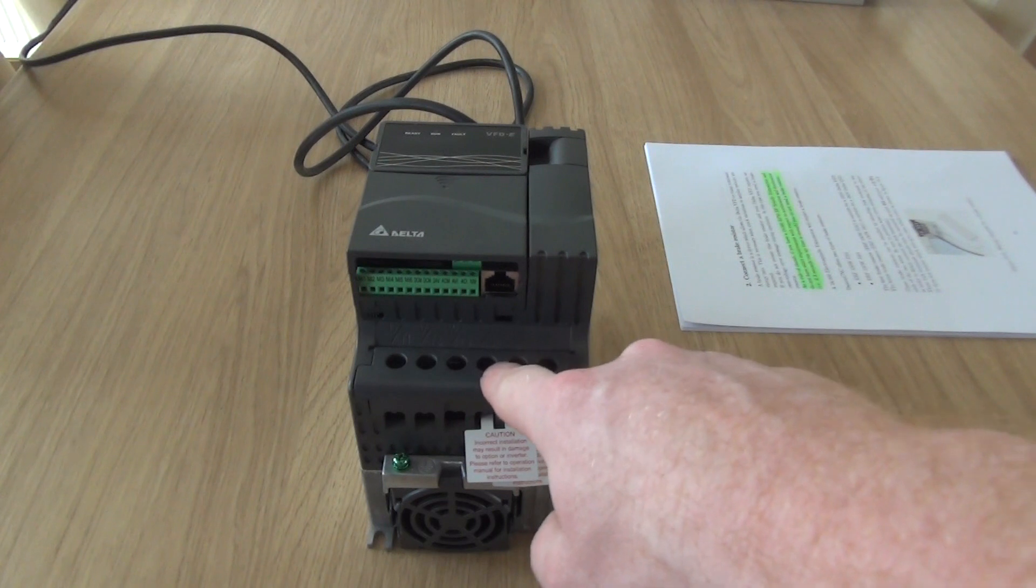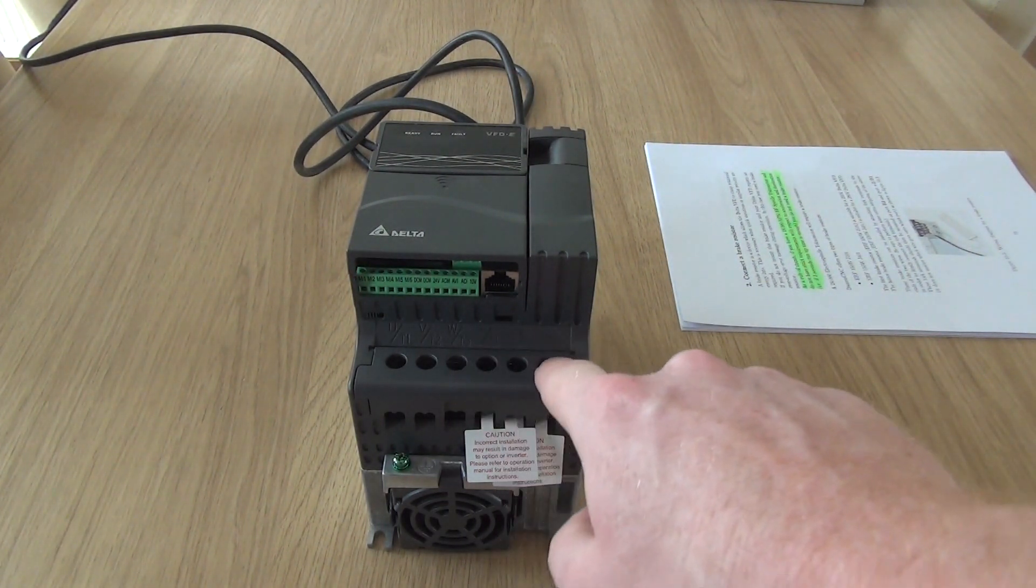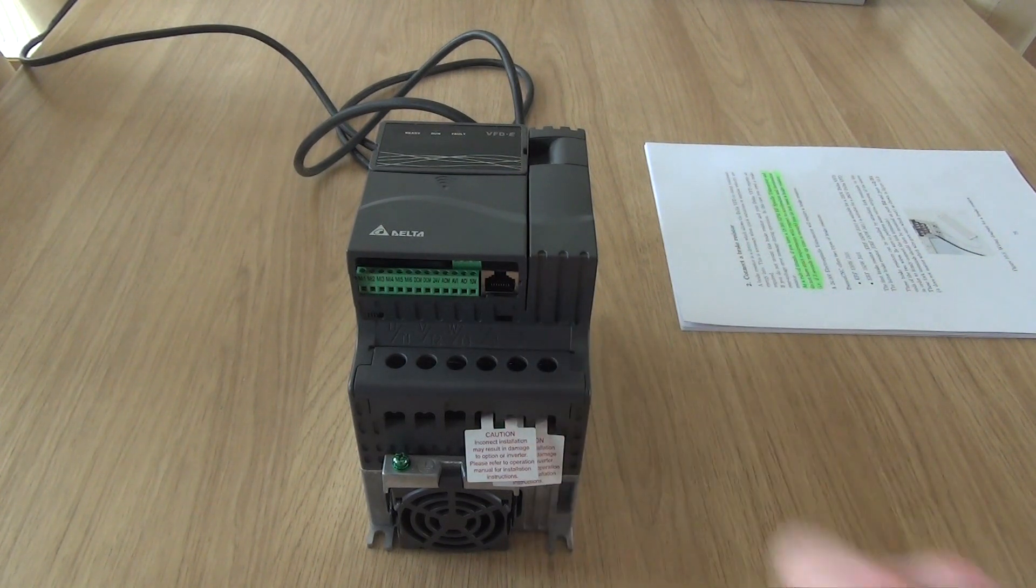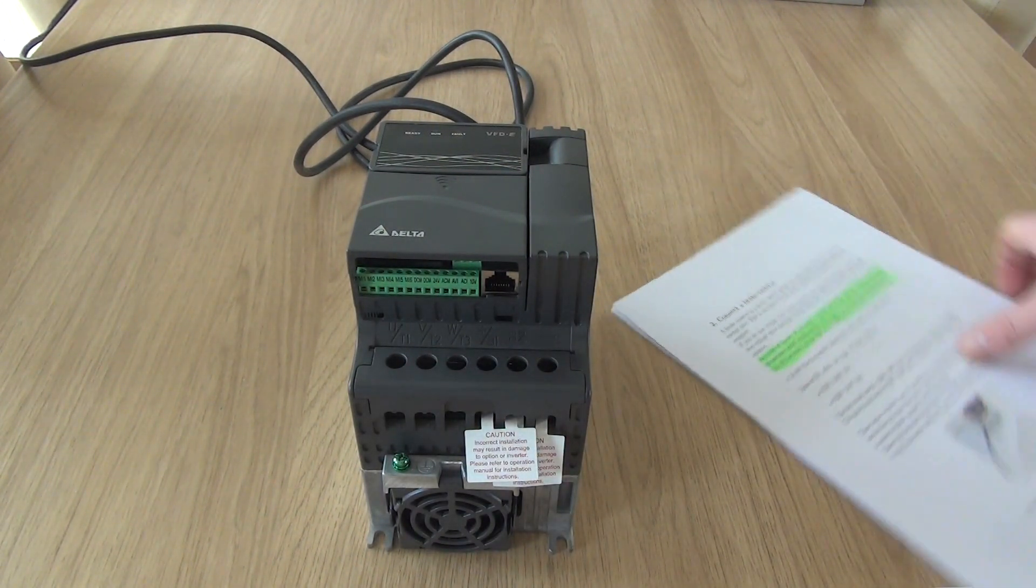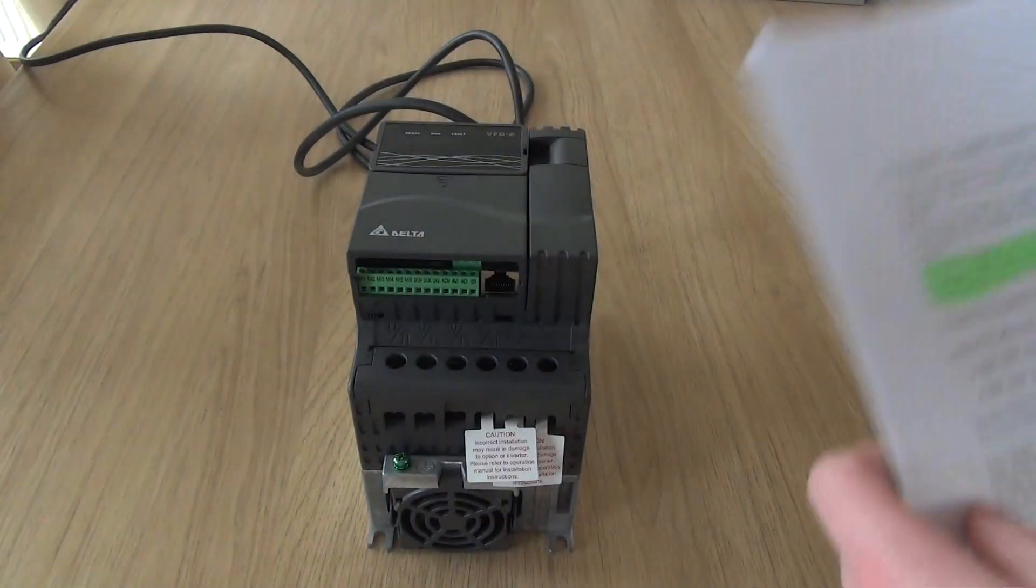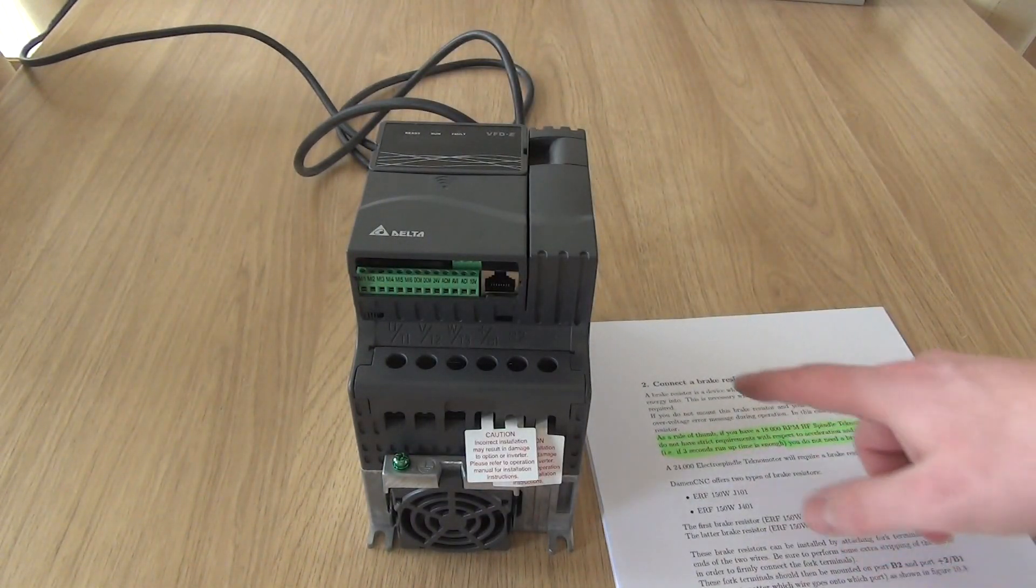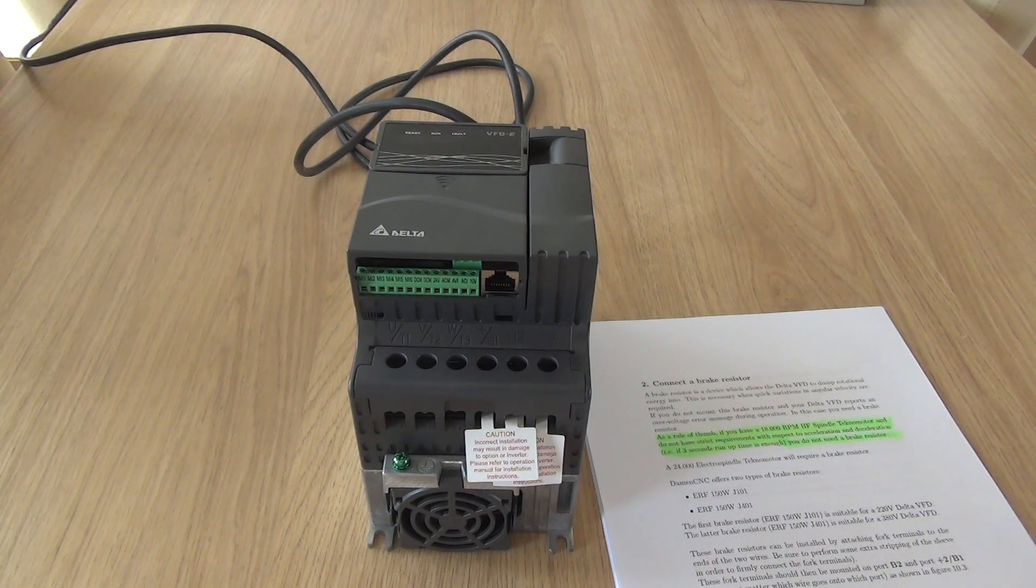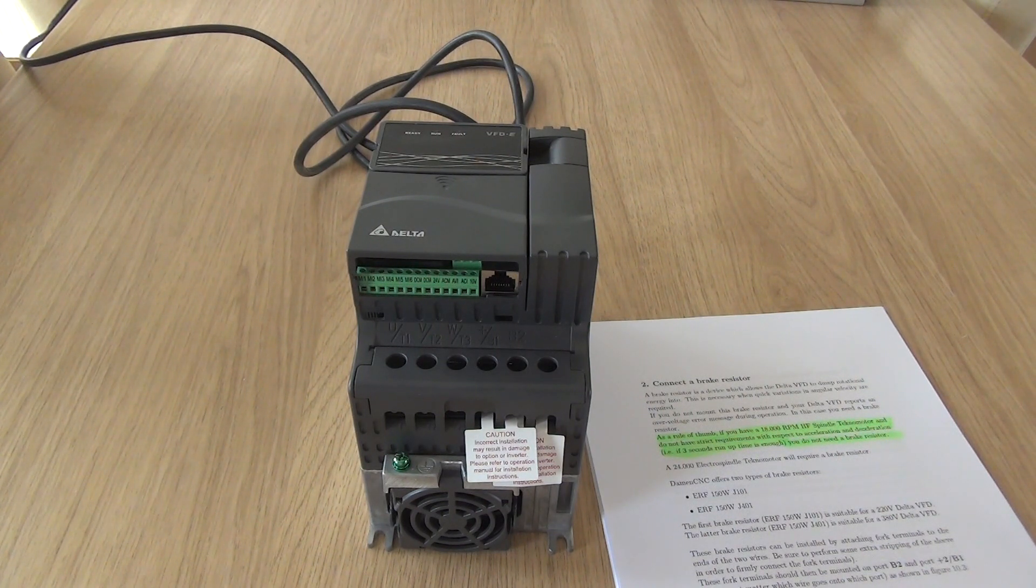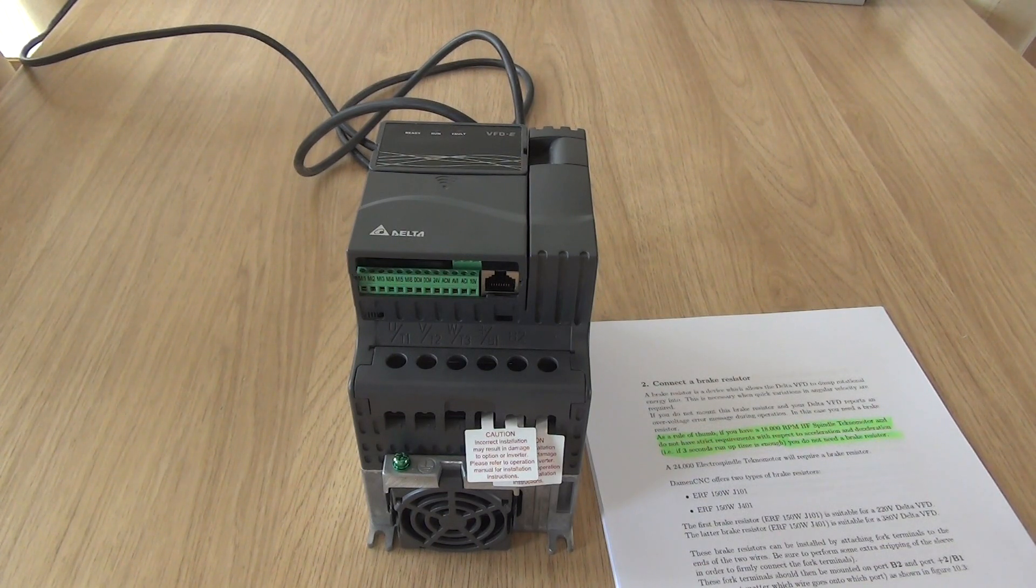Over here you see the B1 and B2 and a negative pole. These are for brake resistors. But if we take note of chapter 2 in the manual or the appendix, we can see that the brake resistor is used to dump rotational energy into. If it's necessary to have quick variations in angular velocity, you really need a brake resistor.